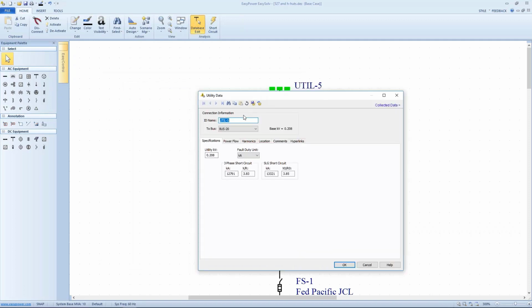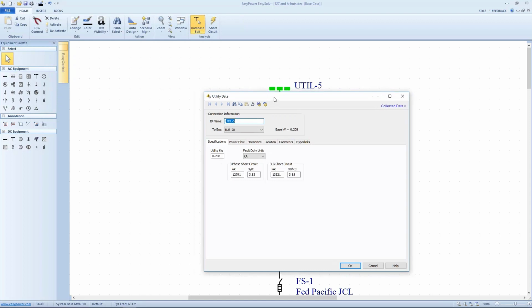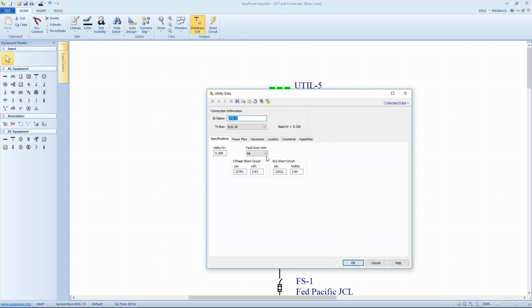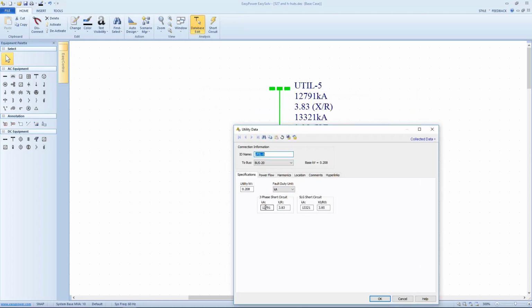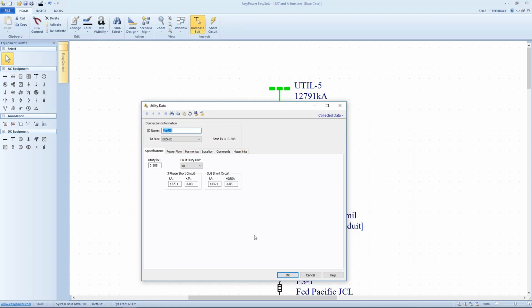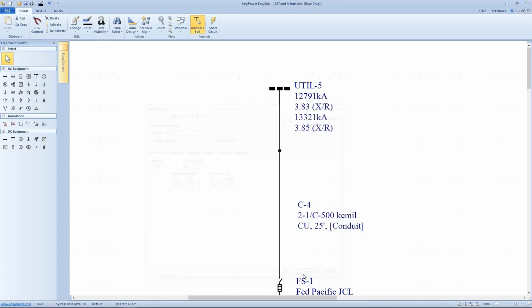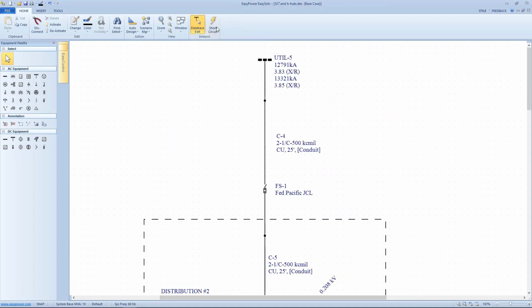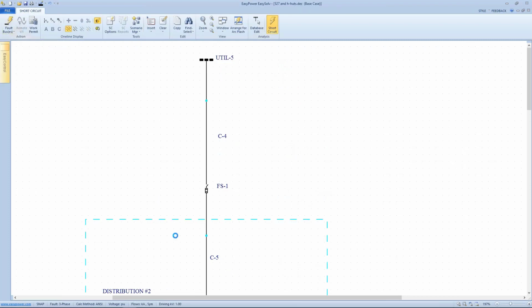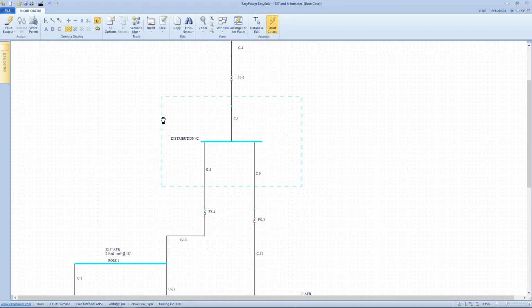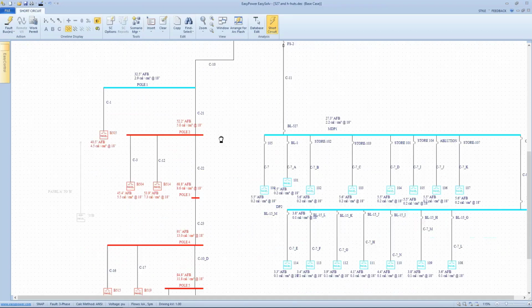And so what we've done is we've taken the utility data icon and modified it with the information that the utility company gave us at the output of the transformer. So in this case, the voltage was 208 volts. The unit is kiloamps, but as you can see, with the numbers that he entered, more than likely he missed a decimal point, and the utility company probably gave him amps, and the tool is asking for kiloamps. So that one issue alone, if we leave this as it is and go back to his initial question, okay, my incident energy seems kind of high, that issue alone might cause us problems.